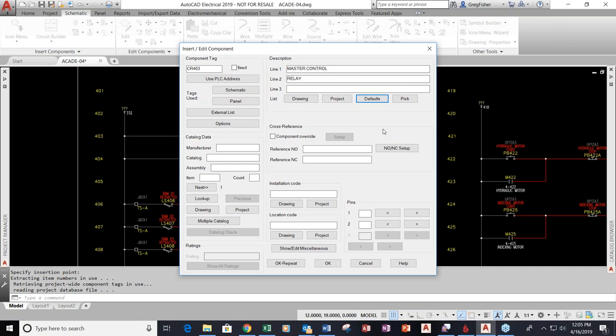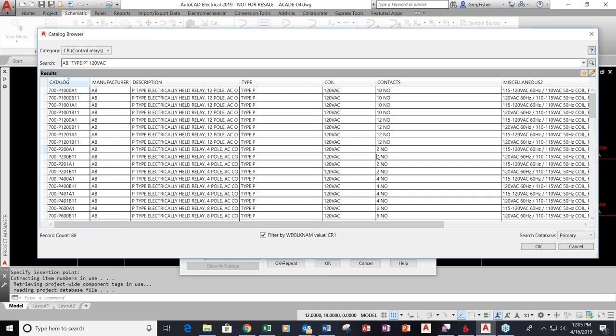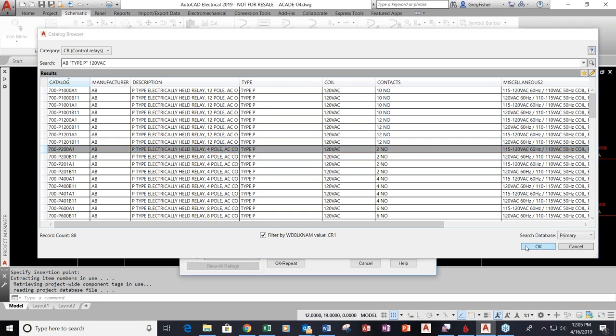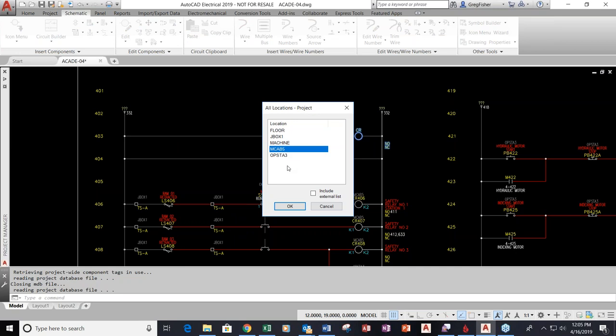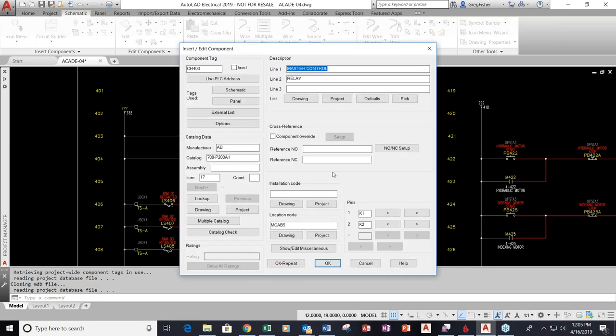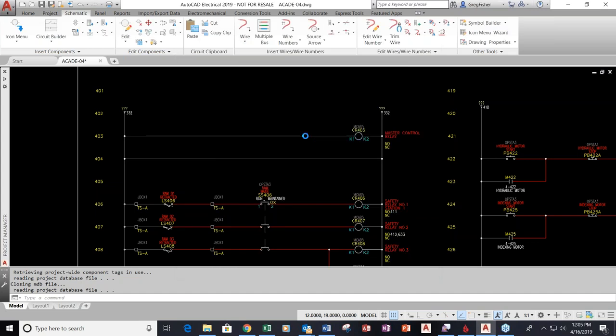There are a lot of features where it will save you typing time. I'm going to attach a part number to this because one of the benefits later on is to run reports — one of those reports is a bill of material. I want to place a part number down onto my symbol, and I can do this at the schematic level or the panel level. Notice when I attach the part number that the pin information automatically fills in. If I were to attach a Siemens part number, the pins might be different and it will adjust accordingly.